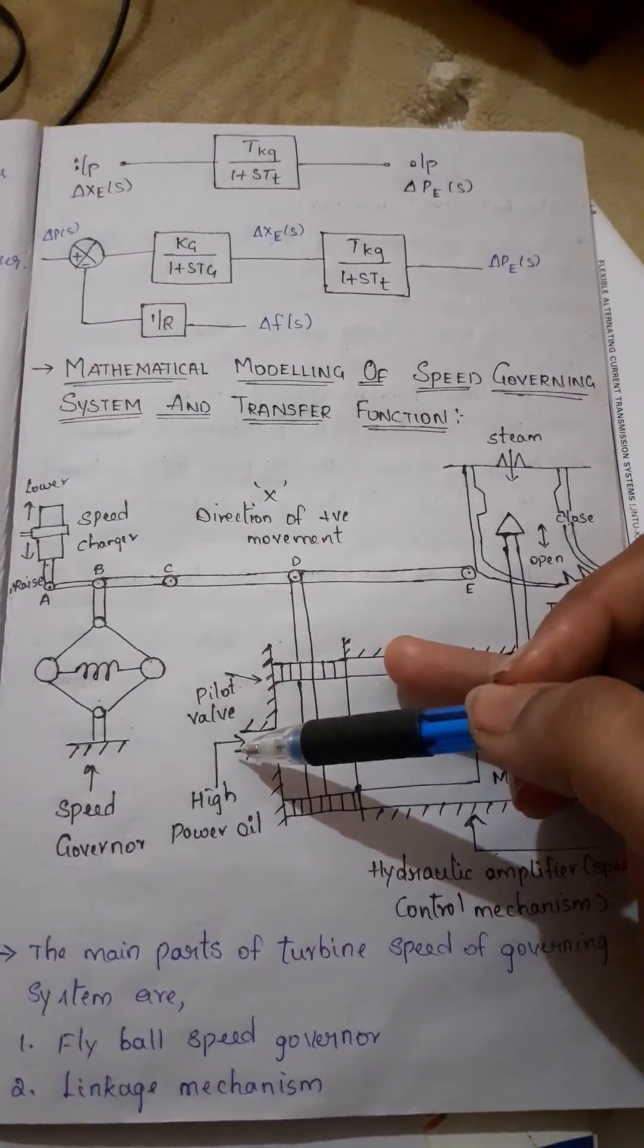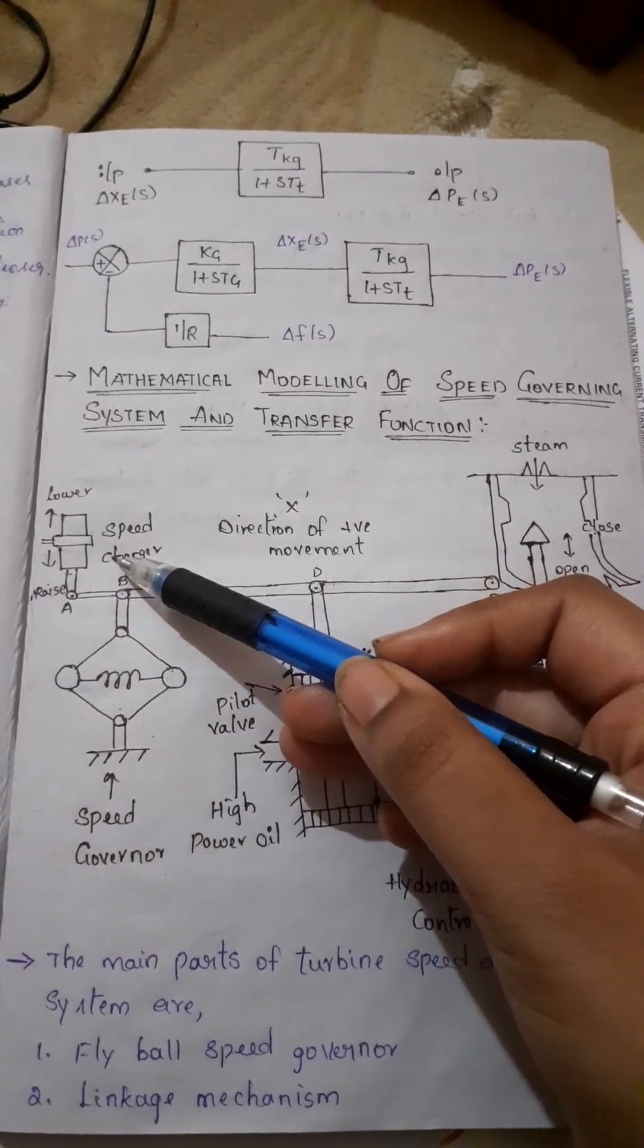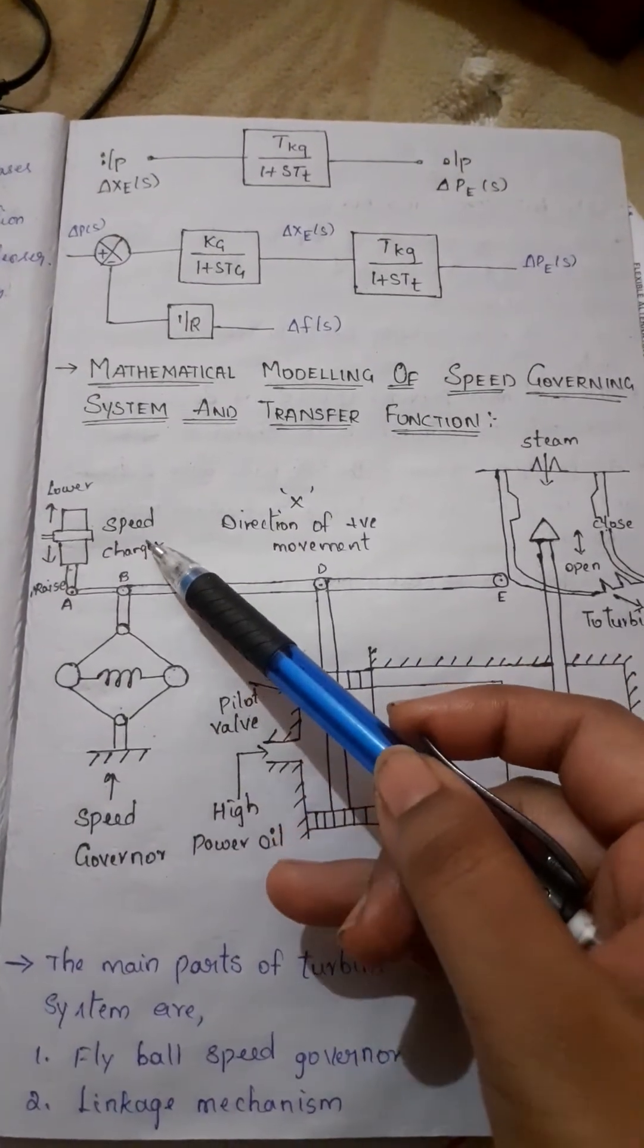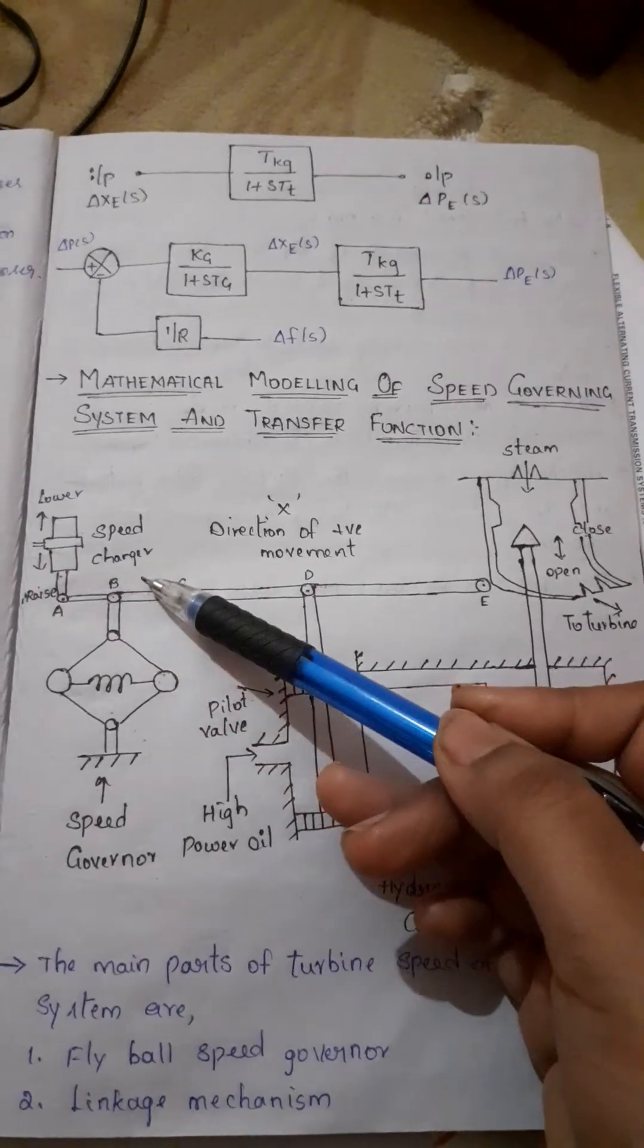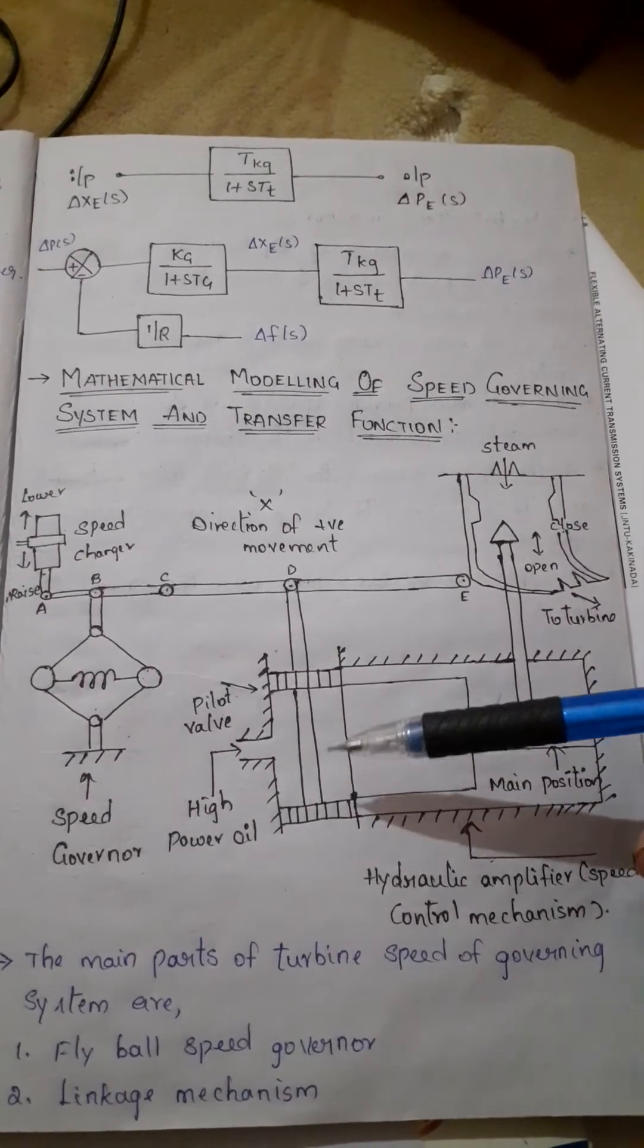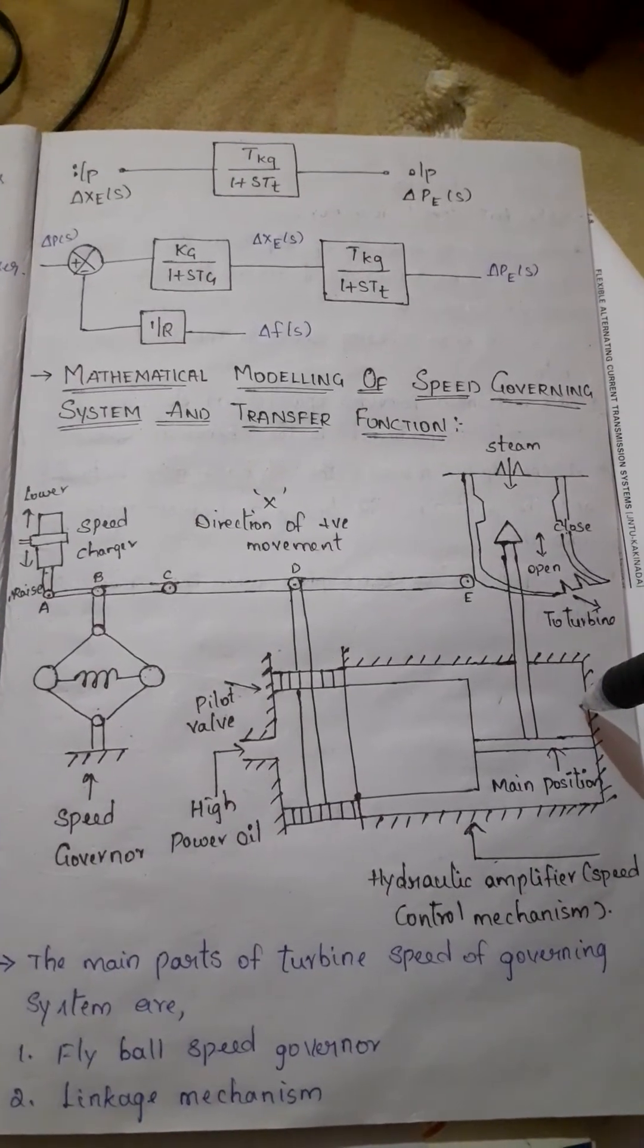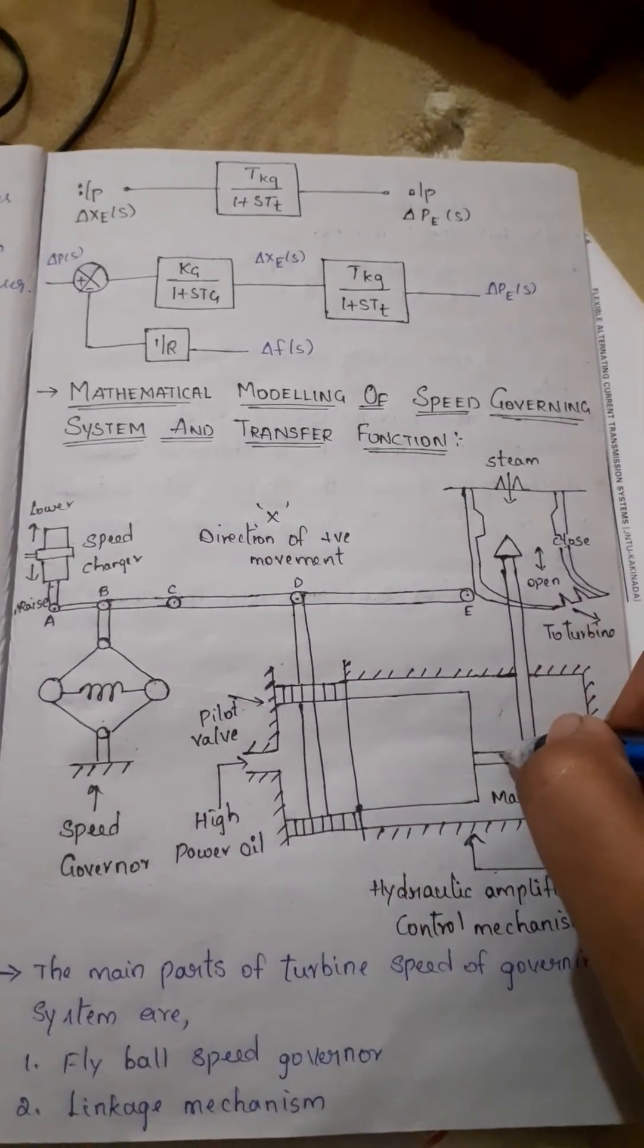The last part is speed changer. It provides a steady state power output setting for the turbine. It provides steady state power output to the turbine. Its downward movement opens the upper pilot valve so that more steam is admitted to the turbine under steady state conditions.